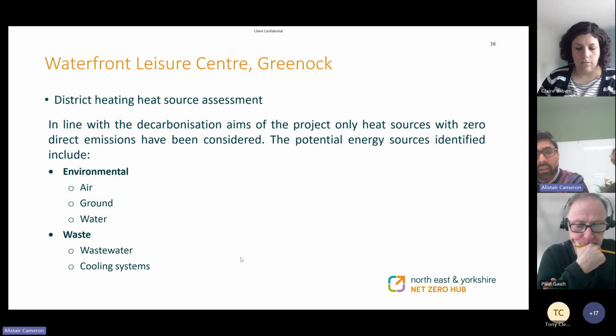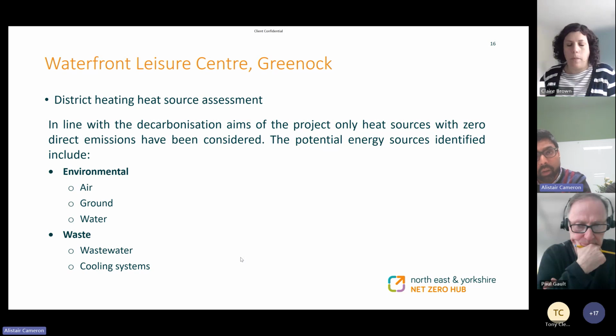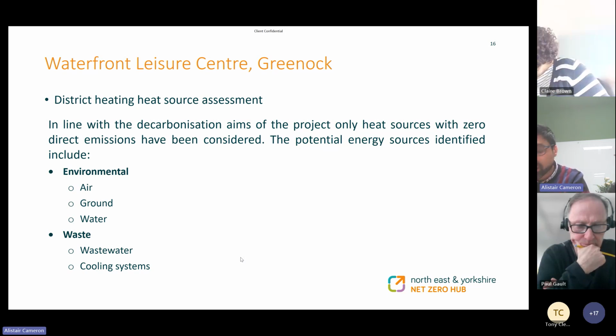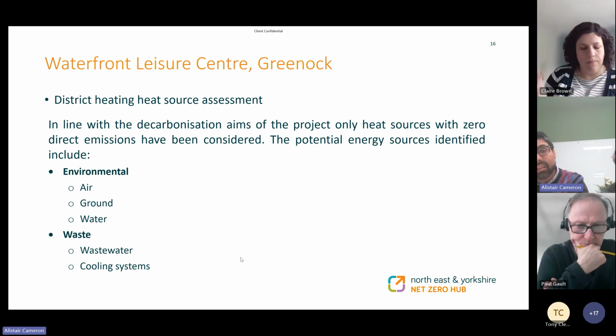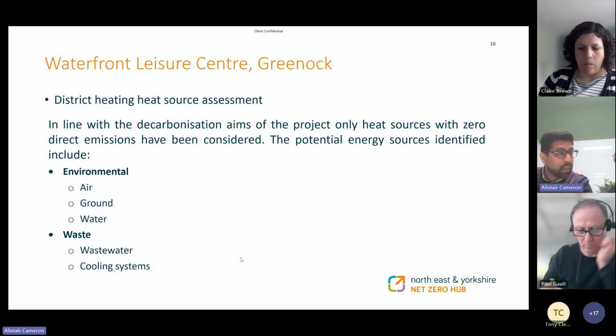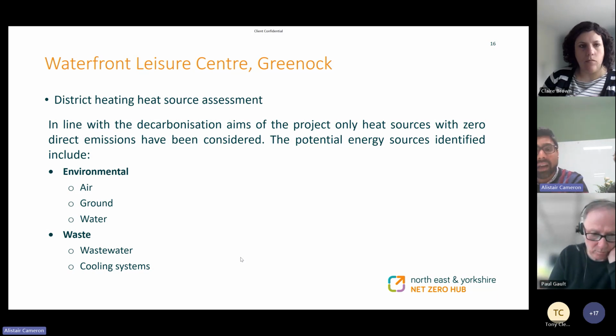When we reviewed the viability of each option, we generally came to the conclusion that using the water from the Clyde was a viable option, and we could capitalise on that and create a low zero carbon heat source. And then second would be the wastewater from the sewage pipe on the A road, which is over 1 metre in diameter and has a high flow rate, and there were opportunities there to capitalise on that and create heat from waste.